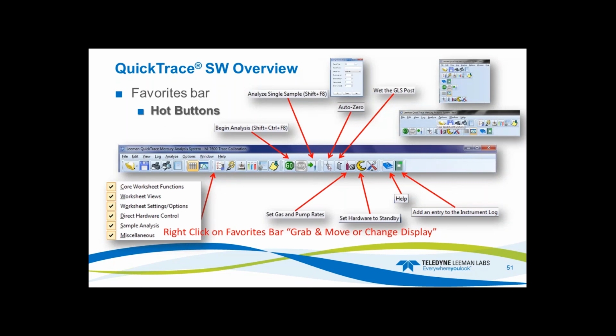On the hot buttons on the menu bar here is a quick list here, so you can begin the run, you can do a single sample read from here, you zero the instrument, you can wet the gas liquid separator, that high gas flow, high pump rate. You can set gas pump. This is a startup icon to get the method going for what your parameters are. Set hardware automatically in the standby. Here you have your help, and here you can add an entry to the log as well.